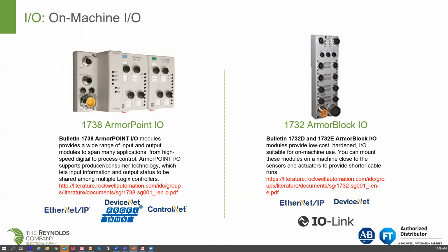Again, it's invisible to you. You'll never see it, but that's the comms it's using. But the IO blocks generally are 2 to 4 points. And the thing about this is we're not putting this in a cabinet. It's out of the box. It can have an IP69K rating. And so it's good for NEMA 4X right out of the box.